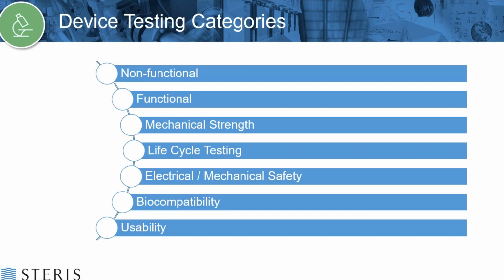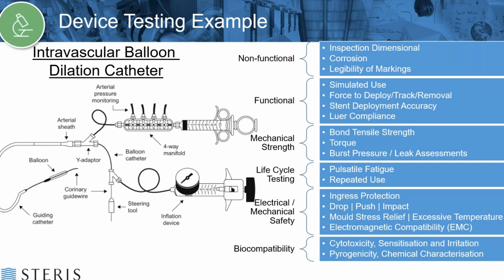So when I get onto device testing, there are a number of different categories that can be looked at for device testing. While they may not be applicable to every device, these 8 should be considered thoroughly for almost all healthcare devices. I've taken an intravascular balloon dilation catheter as an example here, which covers a lot of these categories, and I'll talk through some of the examples of test types that you would typically perform.